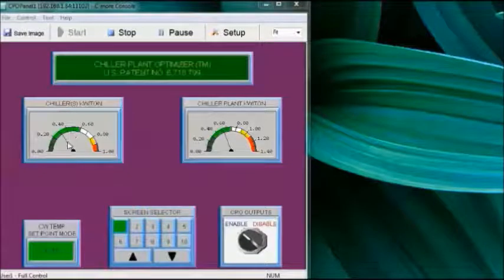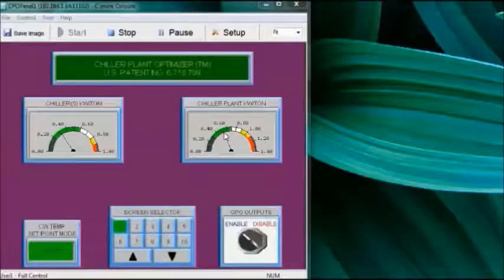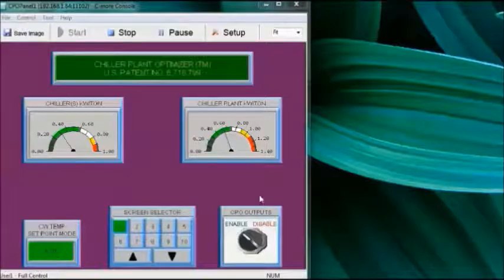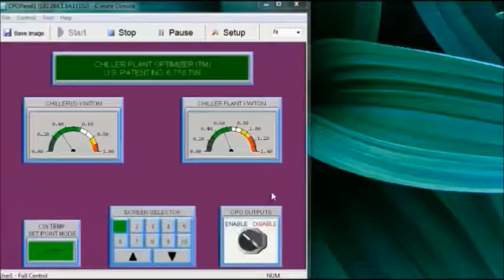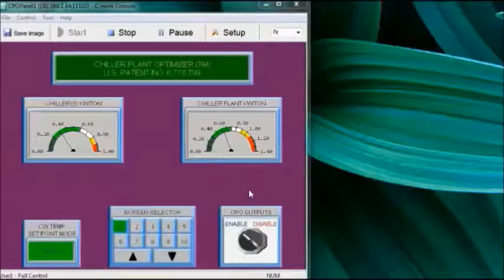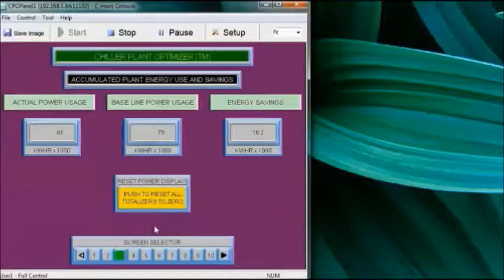It tells us that the chiller is operating at about 0.31 kW per ton and the total plant is operating at around 0.54 kW per ton. The condenser water set point mode is in auto and the outputs are all enabled. This disable function allows us to easily switch to another control or manual control if that's needed to support a maintenance issue. The plant load for this scenario is set at 60 percent, or 600 tons, and the wet bulb temperature is 40 degrees Fahrenheit.